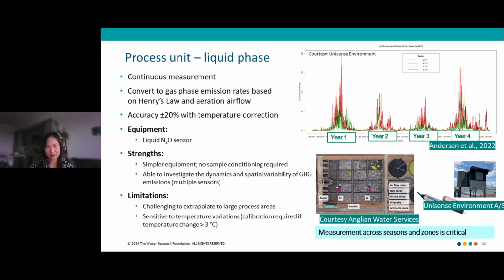So all of the previous methods I just presented can be used for both nitrous oxide and methane measurement. This one is specific to nitrous oxide only. So there is a sensor. Currently, this is the only commercial sensor that can measure the dissolved nitrous oxide in your liquid phase, like in your wastewater. And then you convert this to the gas phase emission based on Henry's law and your aeration airflow rate. So as you can see, the equipment is a lot simpler. You don't need a hood or sample conditioning.